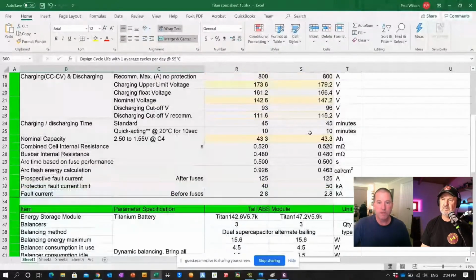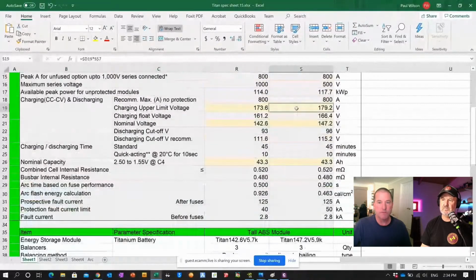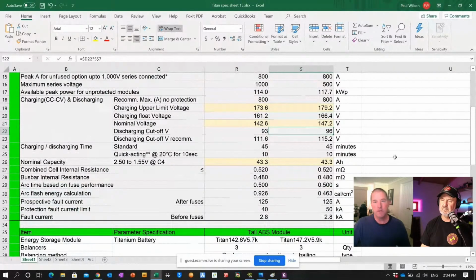Your voltage window here, the upper limit is really 179 volts allowable. The design range is 166, the nominal is 147, and the very bottom we don't want you to go below is 96 volts, with 115 volts being the recommended cutoff.